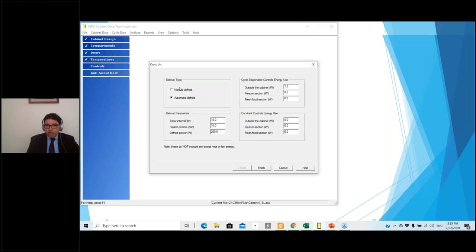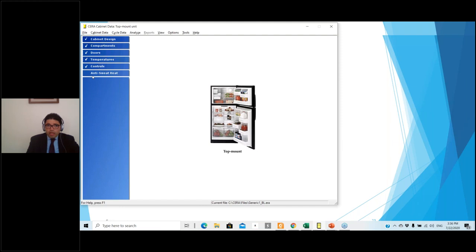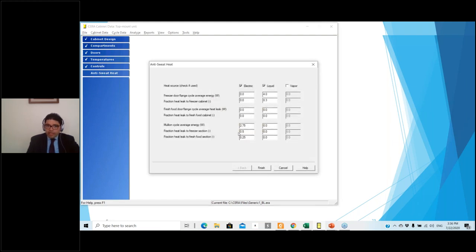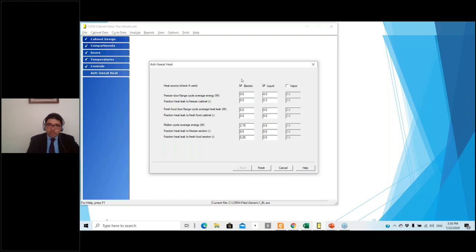Next we define the controls — whether you have auto defrost or manual defrost, and what kind of cycle-dependent control energy is used. In a typical domestic refrigerator there is no constant control. We also define anti-sweat heaters. There are electric, liquid, and vapor anti-sweat heater options. Liquid and vapor anti-sweat heaters add to the cooling capacity for the condenser and are sometimes more favorable. Electric anti-sweat heaters add to electricity consumption and are not necessarily more efficient.